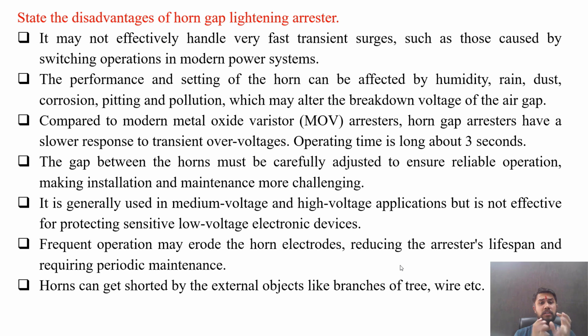The gap between the horns must be adjusted carefully to ensure reliable operation, making its installation and maintenance more challenging. It is generally used in medium voltage and high voltage applications, but is not effective for protecting sensitive low voltage electronic devices. Frequent operation may erode the horn electrodes, reducing the arrestor's lifespan and requiring periodic maintenance. Horns can get shorted by external objects like branches of trees, wires, and creatures like snakes, etc. This will affect the operation and performance of the horn gap lightning arresters. So these are some disadvantages of horn gap lightning arresters.